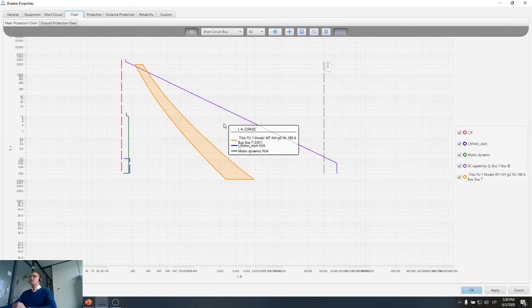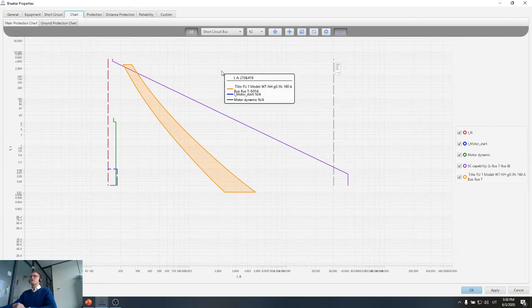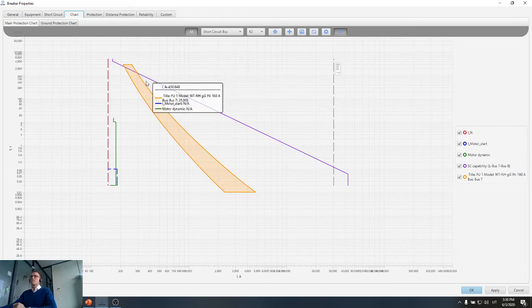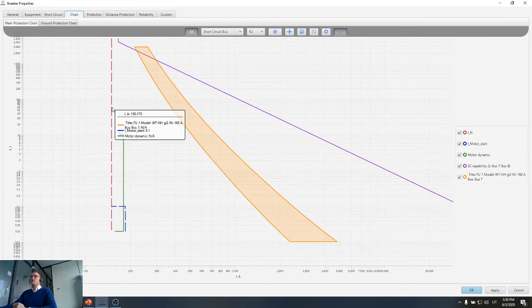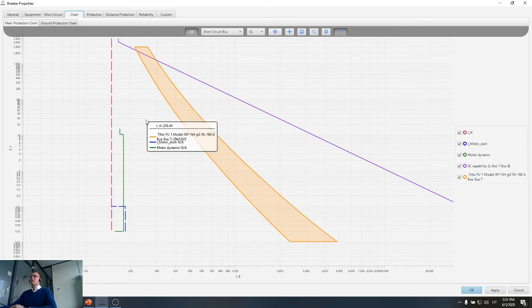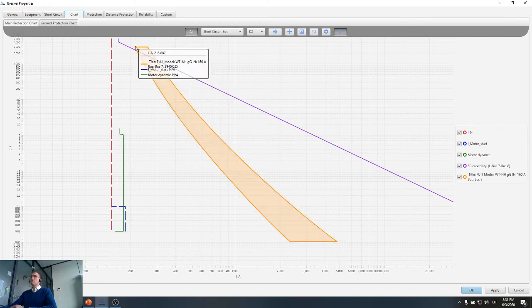So in this chart tab we have several very important curves provided. So let's start by introducing those curves. So first of all, this red dashed line shows the normal current, which we have calculated. So the idea is this, that any protection device should have bigger current rating than our normal current. So we can see by the protection device current and time curve that our fuse definitely has a bigger current.